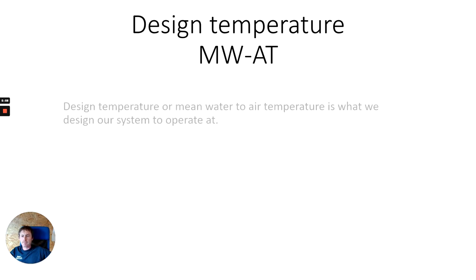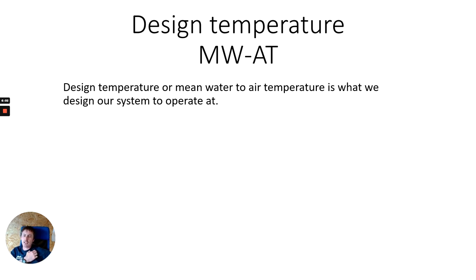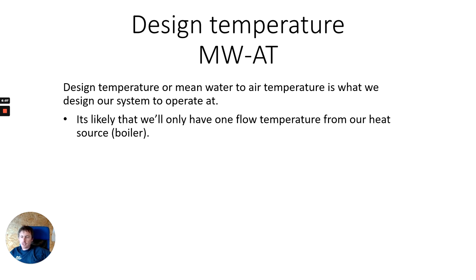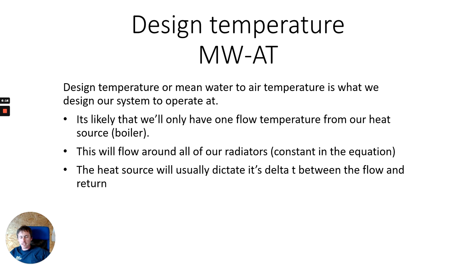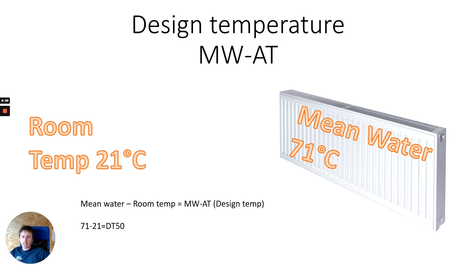The design temperature — mean water to air temperature — is what we design our system to operate at. It's likely we'll only have one flow from our heat source, whether that's a boiler or an air source heat pump, which flows around all our radiators and is a constant in the equation. The heat source will usually dictate its delta T between flow and return. For reference, radiators are sized to BSEN 442 as a standard. In this example, we have a room temperature of 21°C and a mean water temperature of 71°C; subtracting room temperature from mean water temperature gives us 50 — so this is the design temperature, DT50.